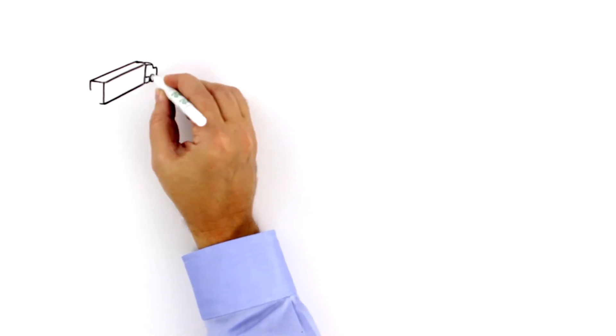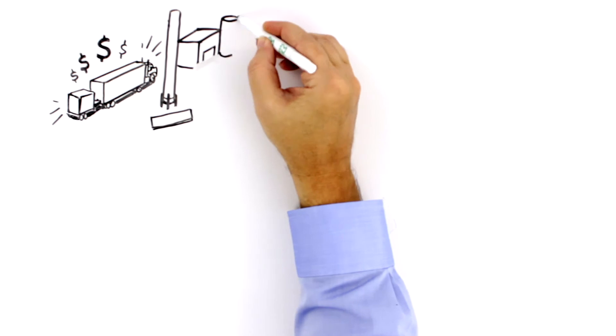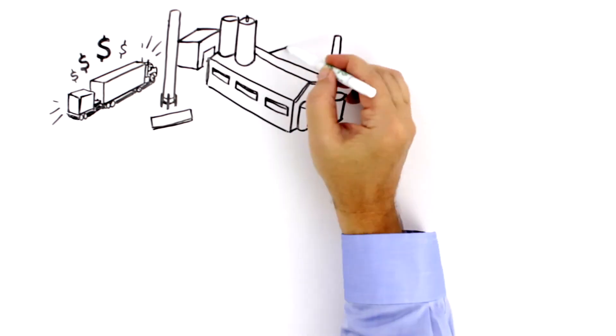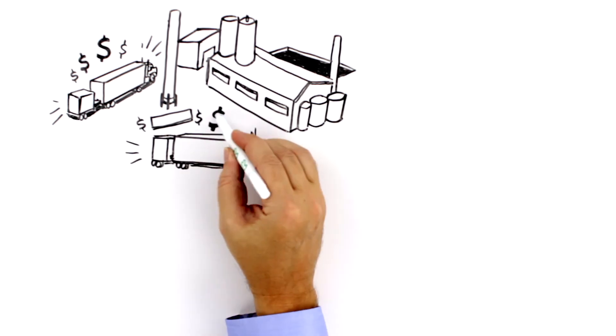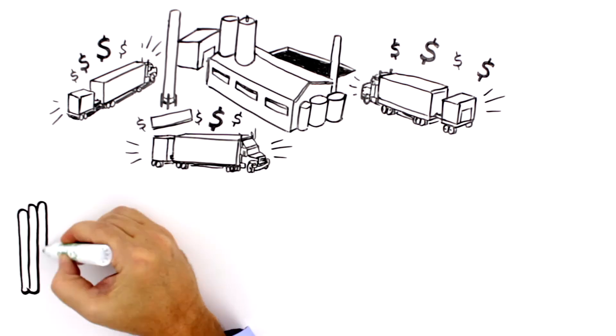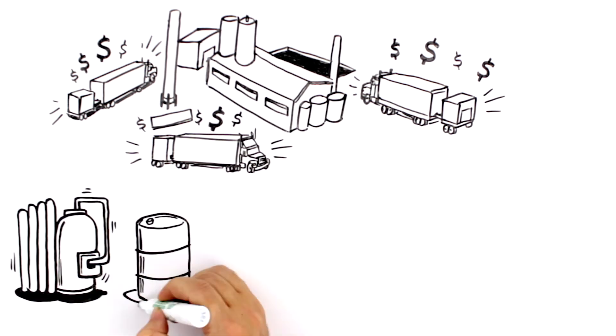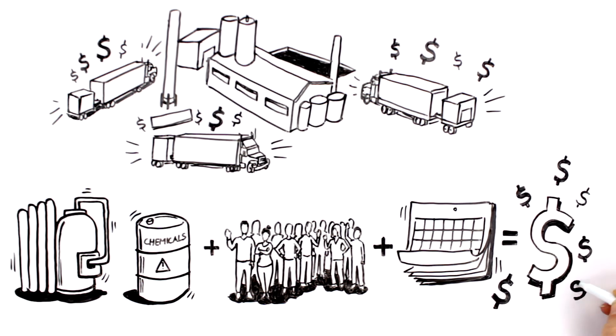Having the appropriate capacity is key, but can be costly. In most trailer designs, flow rate is limited to approximately 800 gallons per minute on surface water applications, forcing the use of multiple trailers to cover the required workflow capacity. This requires additional space, ancillary equipment, personnel, time, and infrastructure, increasing the project OPEX costs.